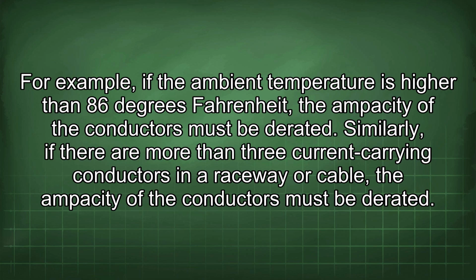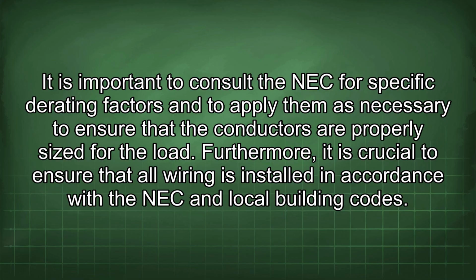Similarly, if there are more than 3 current-carrying conductors in a raceway or cable, the ampacity of the conductors must be derated. It is important to consult the NEC for specific derating factors and to apply them as necessary to ensure that the conductors are properly sized for the load.